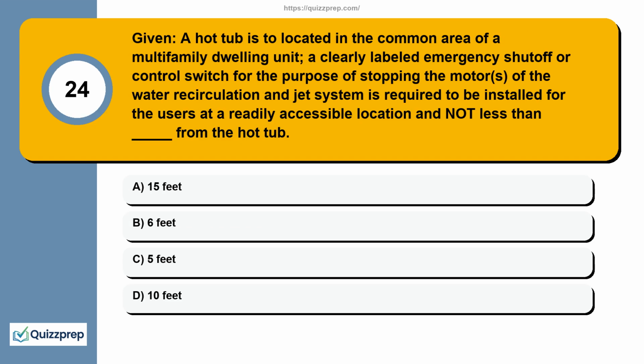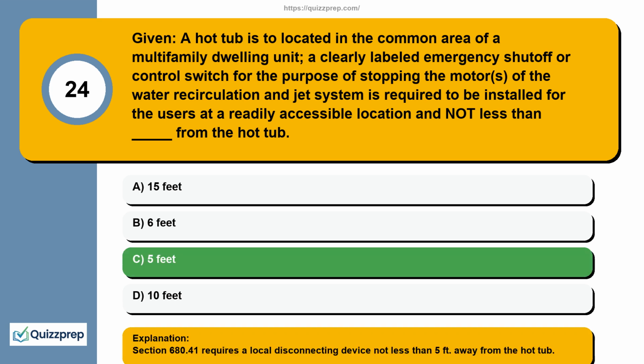Question 24. Given a hot tub is located in the common area of a multifamily dwelling unit, a clearly labeled emergency shutoff or control switch for the purpose of stopping the motors of the water recirculation and jet system is required to be installed for the users at a readily accessible location and not less than from the hot tub: 15 feet, 6 feet, 5 feet, 10 feet. Section 680.41 requires a local disconnecting device not less than 5 feet away from the hot tub.